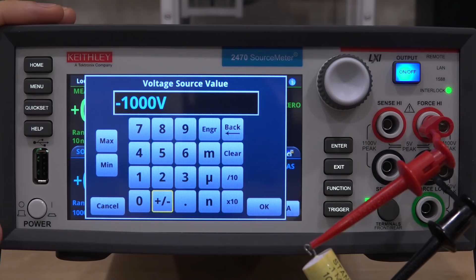And there, look at that. From plus 1000 to minus 1000, no problem. You can see the current is now reversed, and it did that essentially instantly, with a maximum limit of 5 milliamp. It's going to settle down to roughly an equivalent amount of leakage, though there will be a slight difference between the two. That's because one of the two terminals of this capacitor is on the outer casing, so the negative side is on the outer casing, and when you swap the polarity, there may be more charge escaping from one surface versus another. Maybe some minor differences.